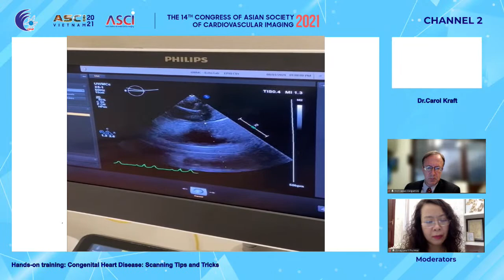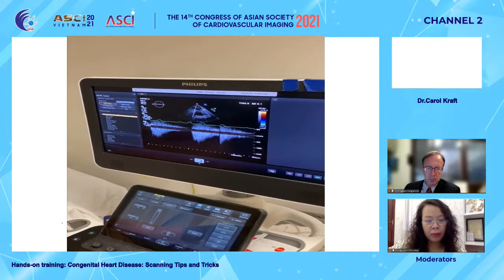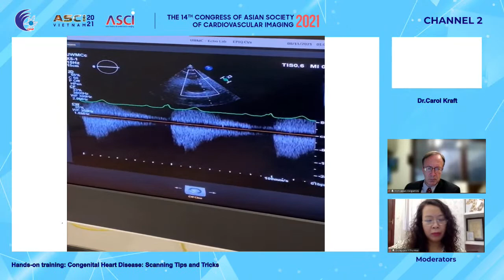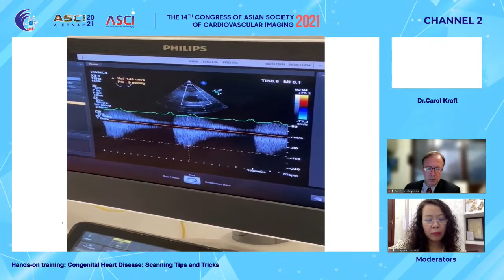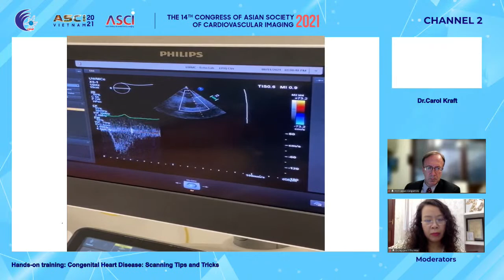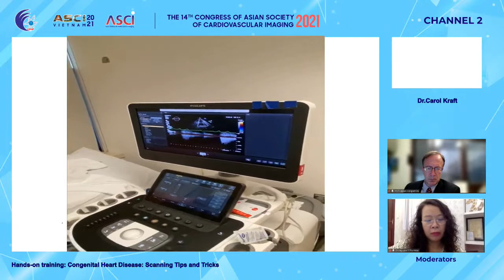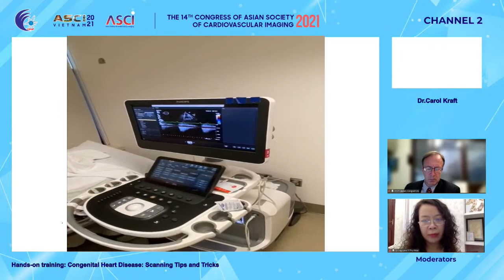And then to confirm that, I can switch into our guided CW, continuous wave. I decrease my overall gain and the velocity scale just to optimize our signal. And we're getting about 1.5 meters per second, or 150 centimeters per second. If I was concerned about it being more significant, again, using the Pedof transducer is something that can always optimize your Doppler signals.